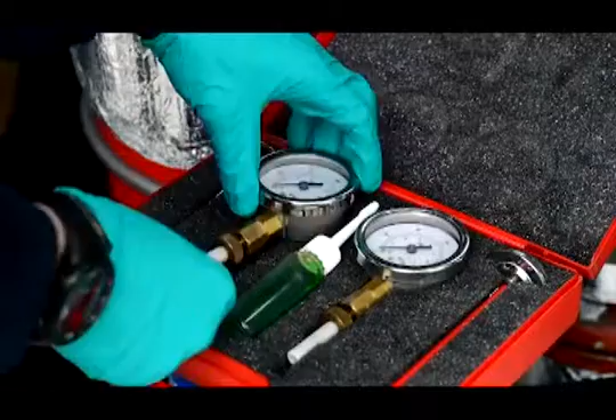Typically the paybacks are 4 years on average, depending on spark gap. But we do sign up to contracts for 15 years plus. Within that 15-year period, we're not only doing routine servicing, which would incorporate oil changes, spark plugs and filters, typically what you'd expect on a spark ignition engine, but we're also doing major overhauls. So one of the key requirements of a CHP scheme is to ensure you've got long-term operational contracts in place, ideally with the CHP provider who installed the CHP, so you maximise the potential benefits from the unit over that period.